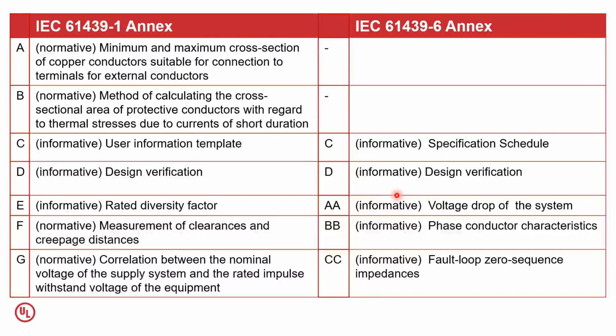Similarly, for the Part 6 standard, there are a couple of informative annexes, as you can see from here. The one is the informative in the context of the specification. As you can see here, the specification schedule both look very similar, except that this is more related to busways, whereas this is more of a general rule application for all the switchgear and control gear assemblies. Then you have Annex D, more specifically brought out for busways, which is slightly different from what you find in the Part 1 standard.